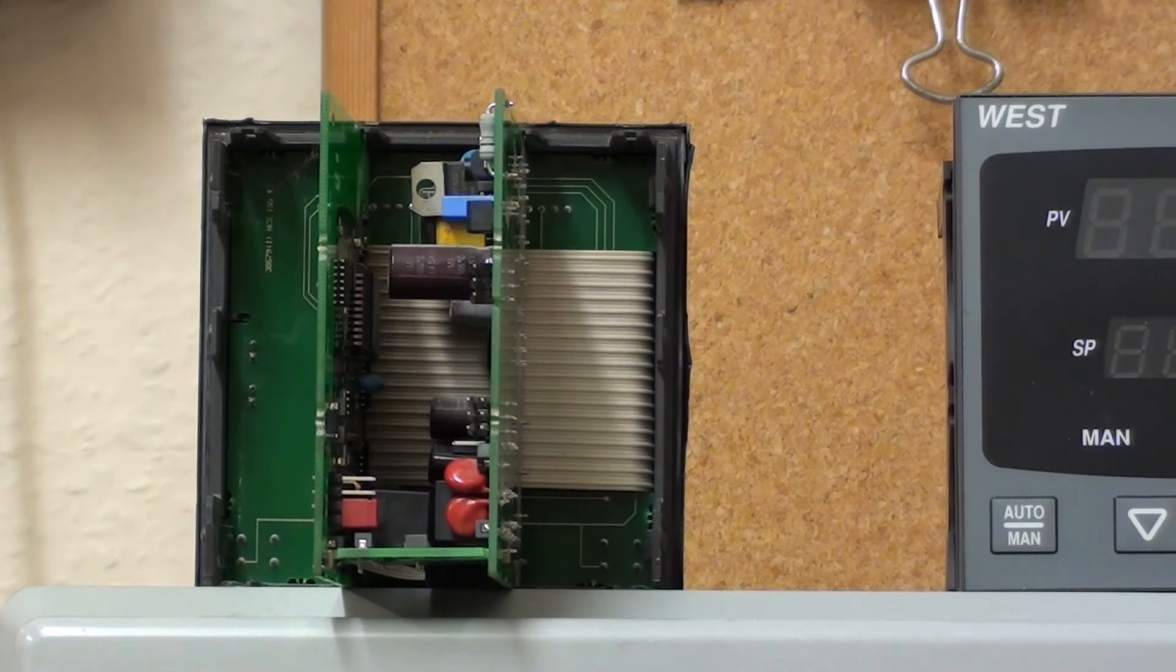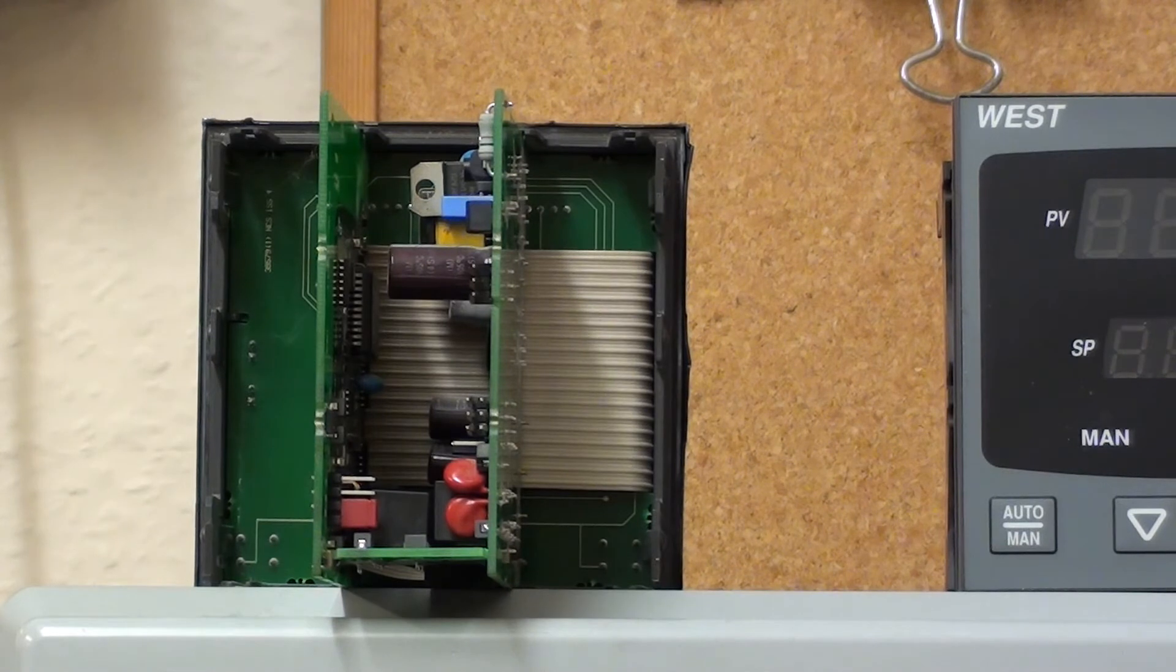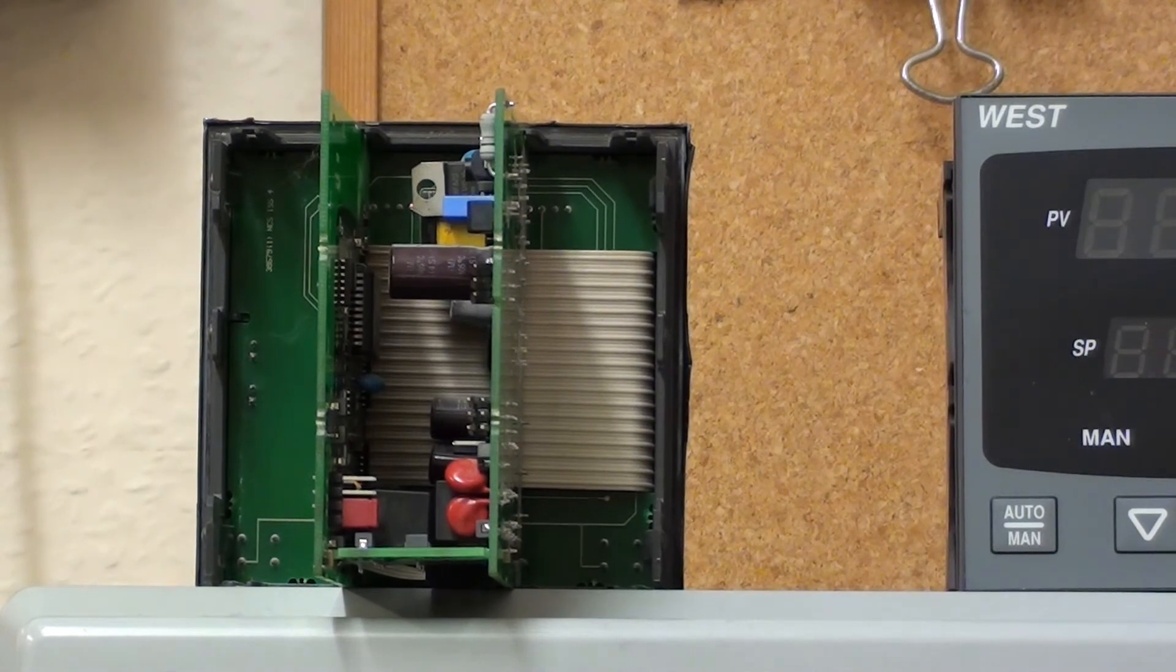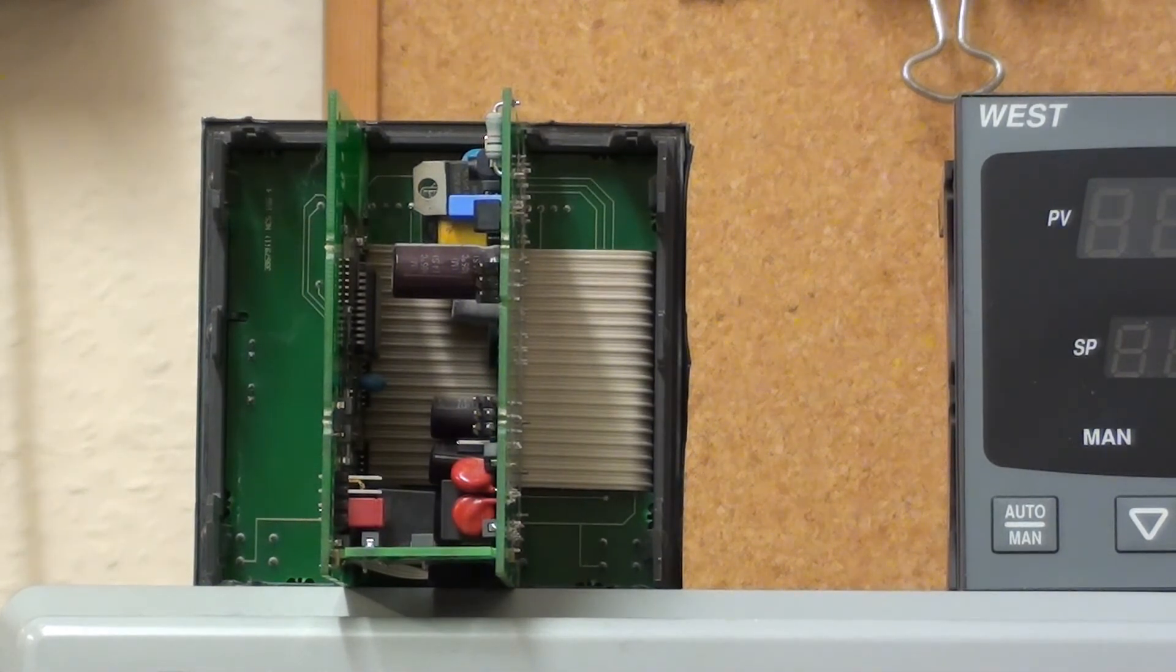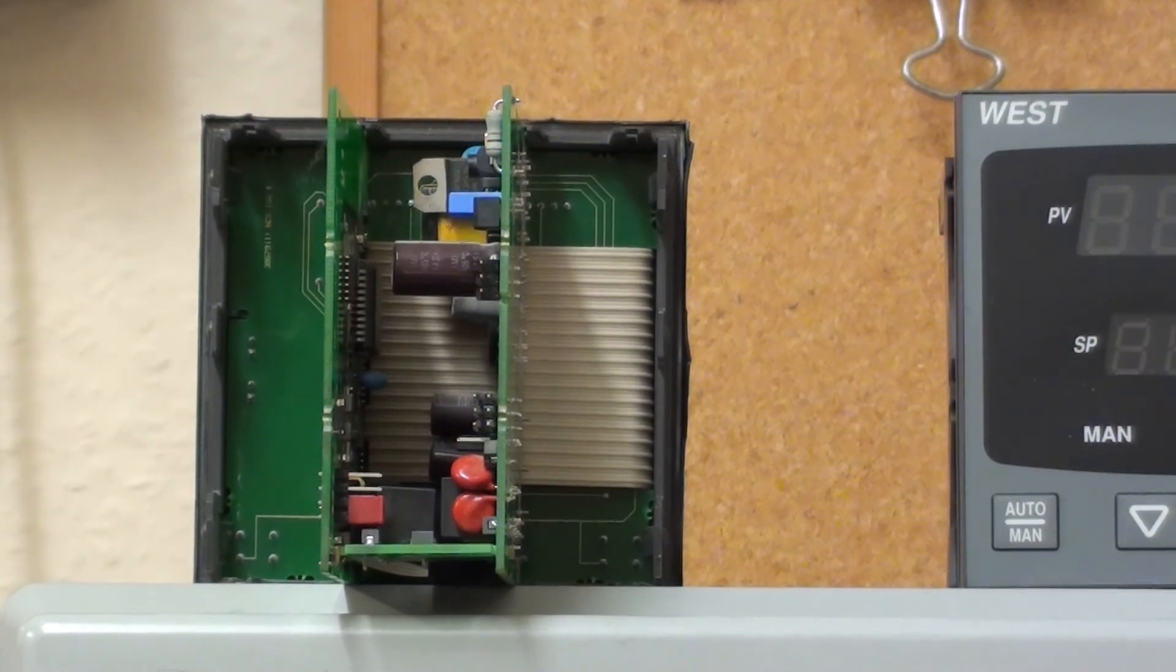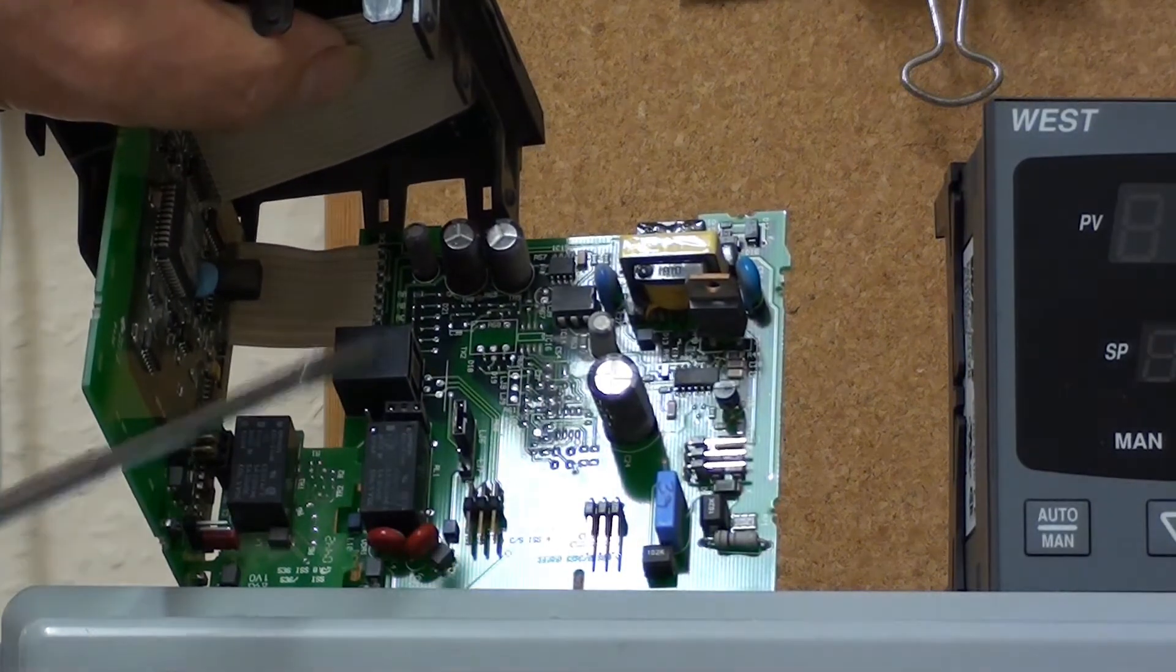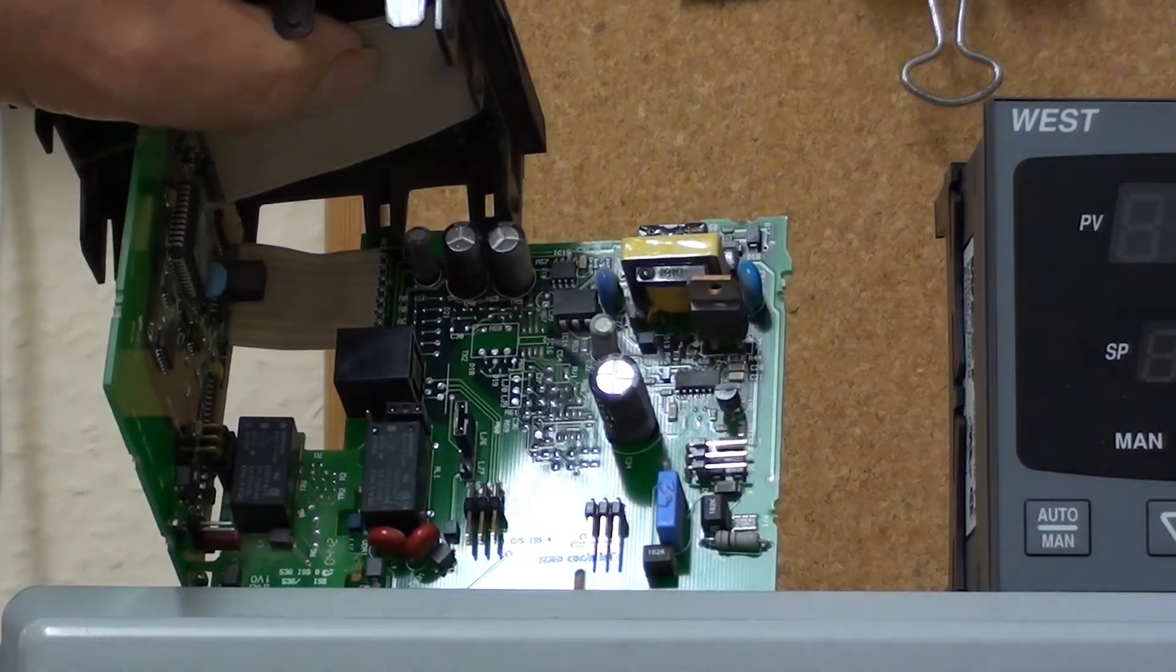In the N4170 there were link jumpers for the type of outputs required. Again, this isn't required on the latest P4170 model. Looking here you can see the link jumpers for the output.